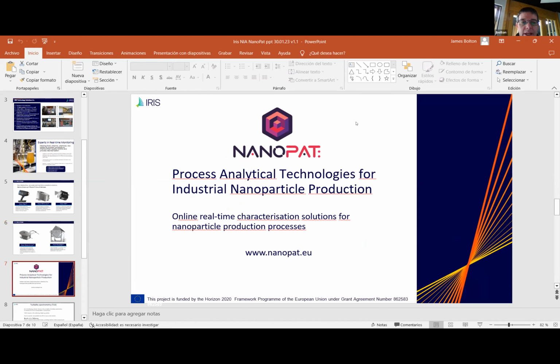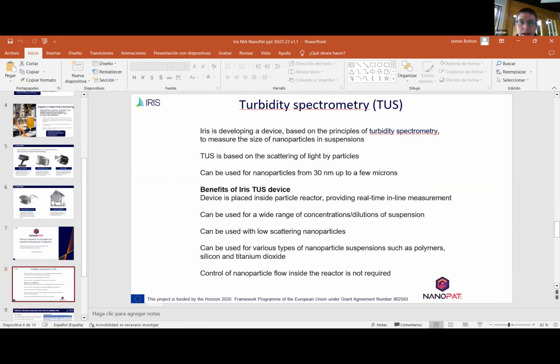So where we fit into the technical part is we are part of the NanoPat project, which is about online real-time characterization of nanoparticle production processes. It's an EU-funded project. And we are developing a device based on the principles of turbidity spectrometry to measure the size of nanoparticles in liquid suspensions. Turbidity spectrometry is based on the scattering of light by particles. This device can be used for nanoparticles from size 30 nanometers up to a few microns.